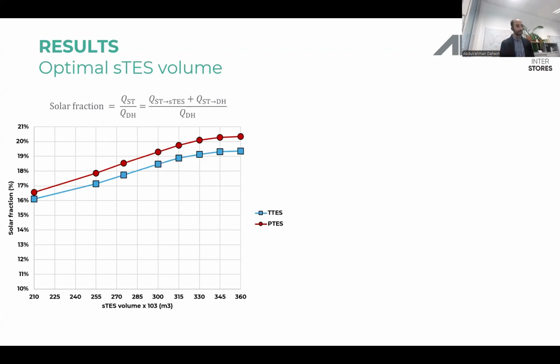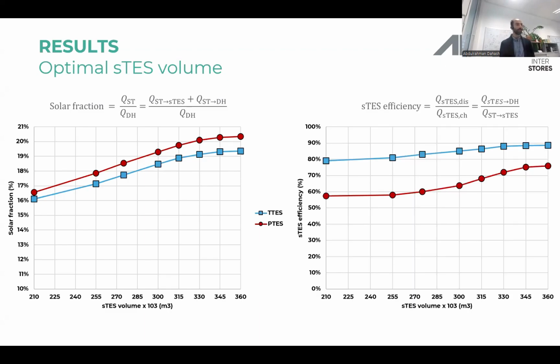If we want to consider another indicator, that would be the thermal efficiency of the seasonal thermal energy storage. So on the right hand side, you see in here the efficiency of the seasonal thermal energy storage for the two technologies. And what you see in here is that the tank thermal energy storage has a minimum efficiency of around 80% that increases up to 90% for the volumes that we are considering, while for the pit thermal energy storage, the red line in here, it starts slightly below 60% up to 75%, as you see in here.